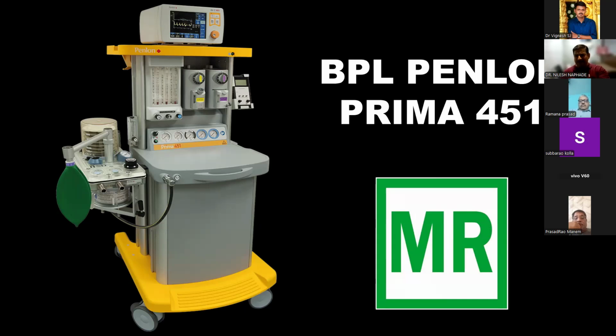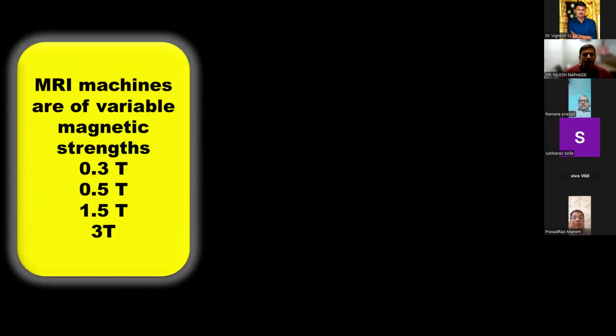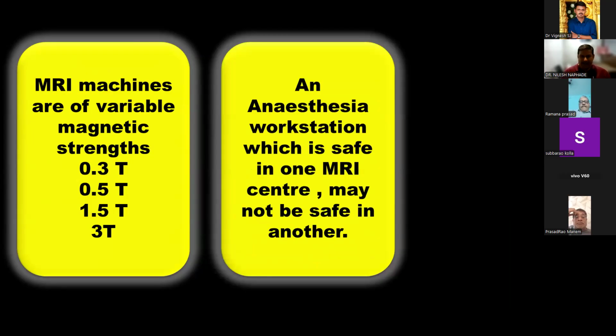I'm just giving you examples. There might be more also. I'm just giving you one example of each place. I want to give one scenario to all the listeners. MRI machines are of variable magnetic strengths: 0.3 Tesla, 0.5 Tesla, 1.5 Tesla, sometimes 2 Tesla and 3 Tesla. The more the Tesla, the stronger the magnet of that machine. An anesthesia workstation, which is safe in one MRI center, may not be safe in another.